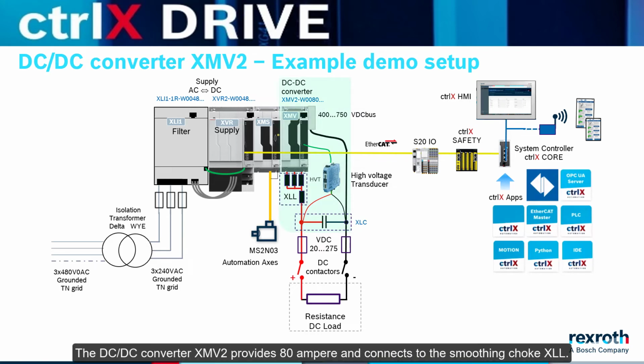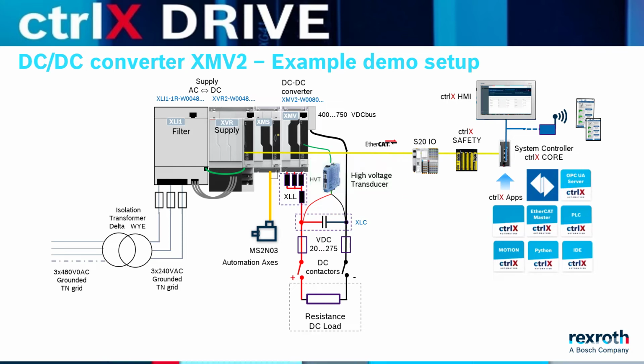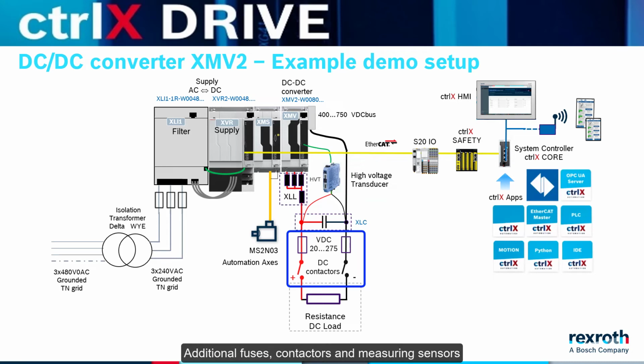The DC-DC converter XMV2 provides 80 ampere and connects to the smoothing choke XLL. The XLL output is connected to the smoothing capacitor XLC where the DC output voltage is measured with a high voltage transducer for closed loop control by the XMV2. Additional fuses, contactors and measuring sensors suitable for the DC output voltage range may be required for the application.